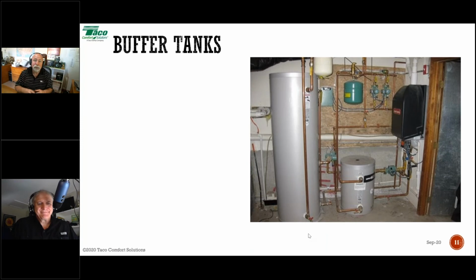Okay, right. So it could be better. Don't get me wrong, it could be better, but it's not the end of the world. Again, that is associated with using a fixed speed circulator at that point. There are some other things, like I personally have done in my place, where I put a delta T controlled circulator as my boiler primary because I don't have that third party signal that I can control 0 to 10, etc. So, John, go ahead. I've gone longer than I should have.